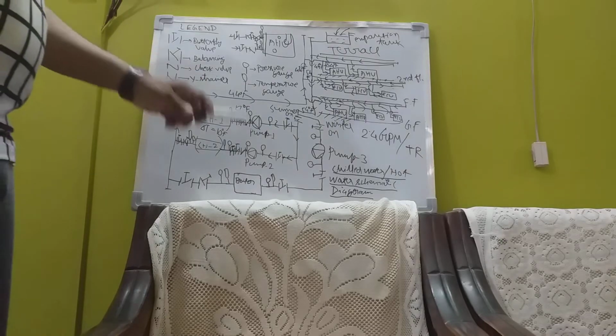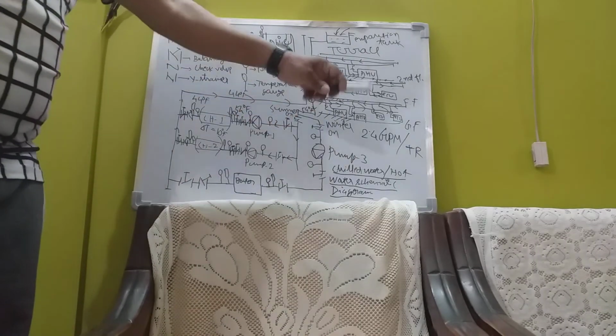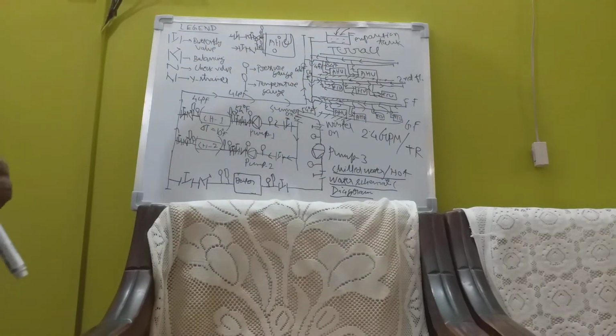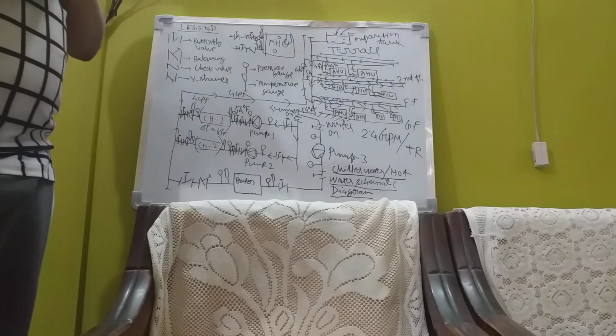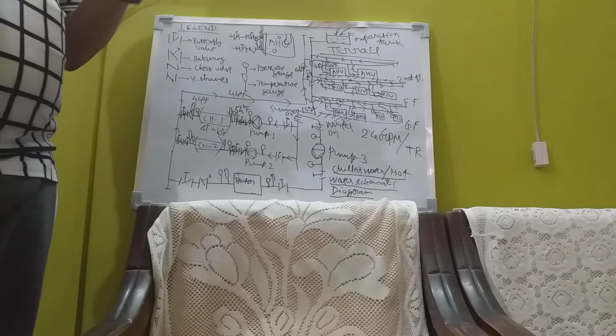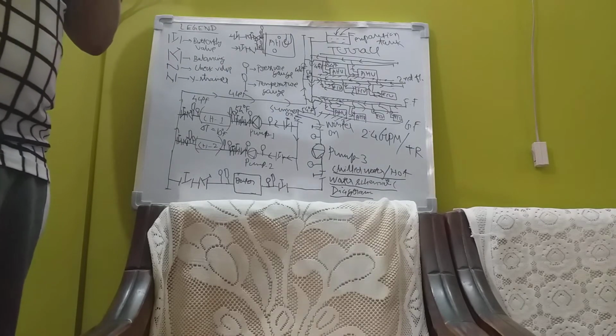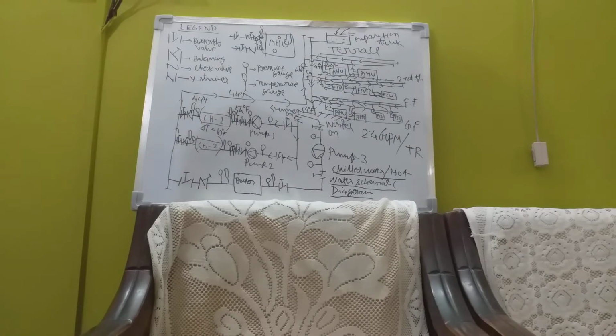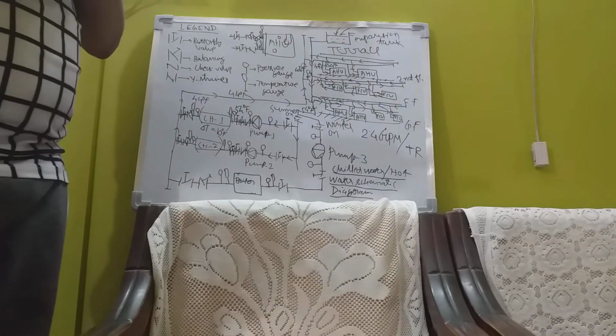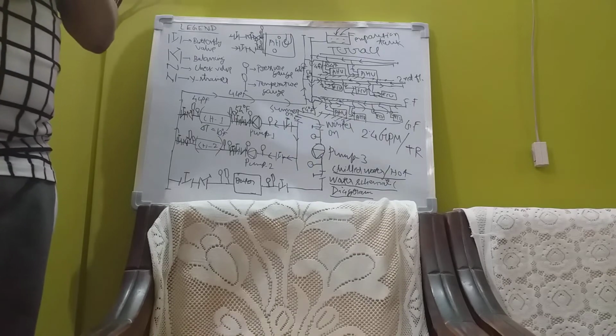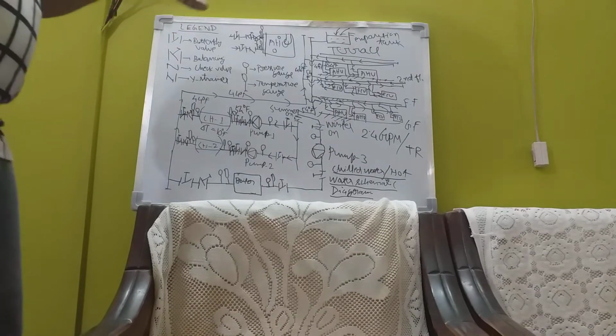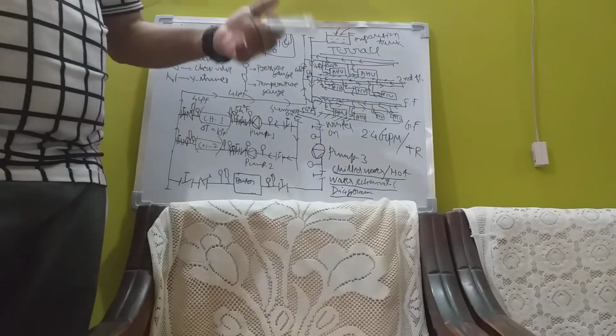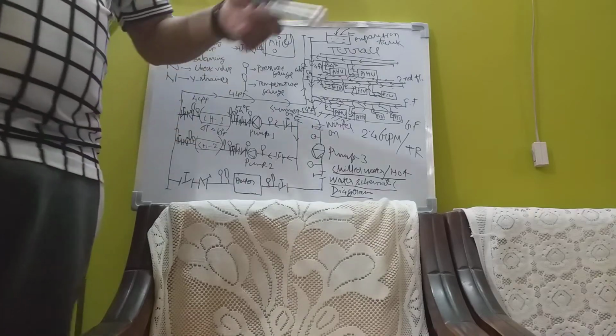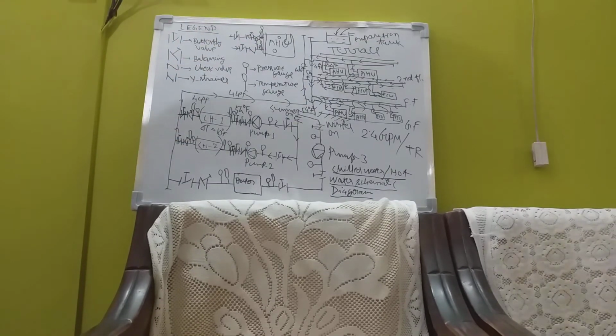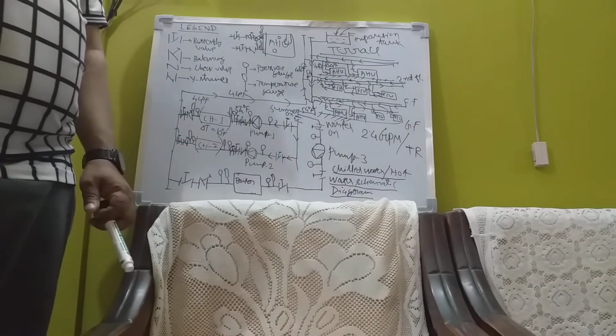Again I am telling you, in Western countries the hot water system is totally separate. But there are two problems with a separate hot water system and chilled water system. We put them separately. The problems are, number one, space. The hot water system will take a lot of space, the chilled water system will take a lot of space, and we don't have the space. In a place like Nehru Place, a typical example in Delhi, it is very congested. You cannot put both the pipes together.